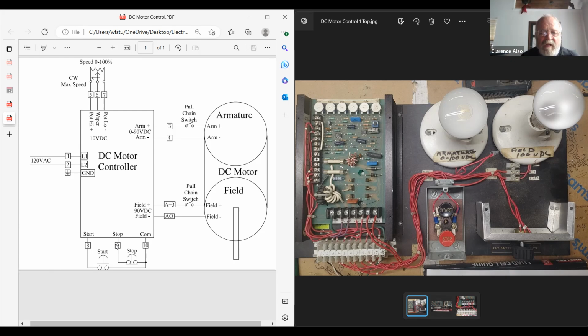Now let's check out the start button. So if we're going to start with the start button, what two terminals am I hooking up to? 8 and 10. Okay, and what are you expecting on 8 and 10, what kind of reading? Looking at the graph right now, you see OL. Good job. And then what if you push the button? You should receive zero. You just operated it correctly. Did you just check that out with your ohm meter?